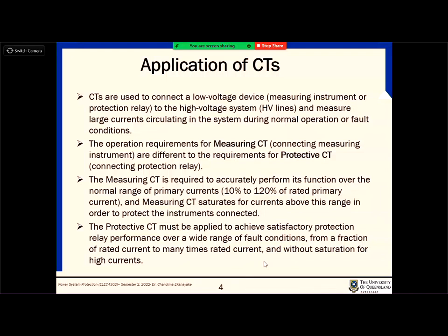Yeah. So for the protective CTs, what happens if a protective CT saturates for a fault? Do you allow the protective CTs to saturate? No. They don't have to be accurate, but they shouldn't saturate even at, let's say, 10 times the load current, right? Because the fault current might be very, very high. So from the saturation point of view, protective CTs perform well, or they don't go into saturation. Those are the major two differences between them.